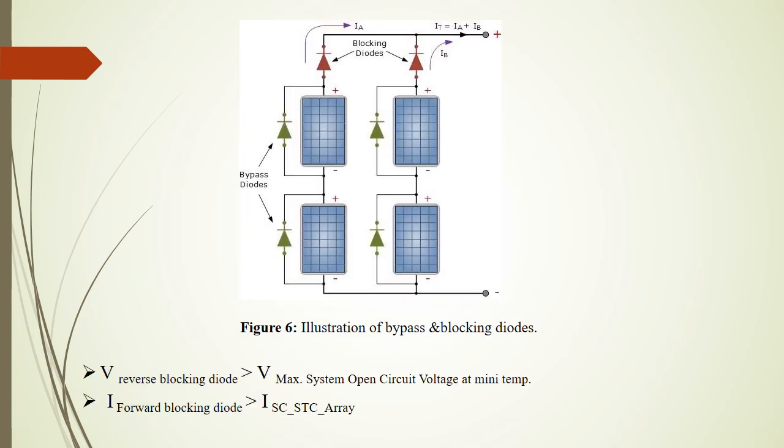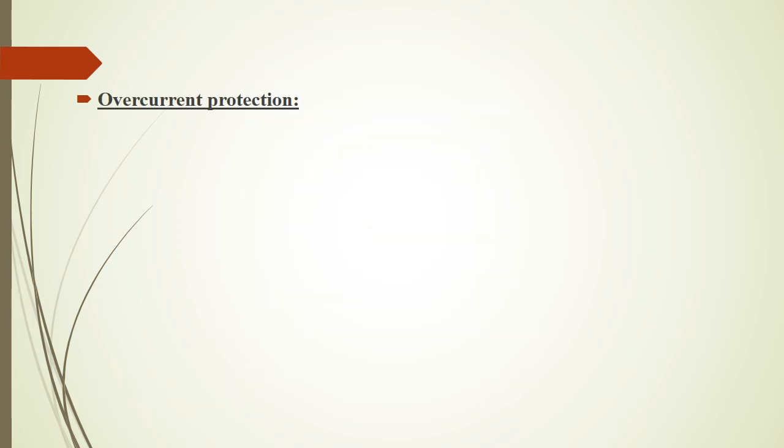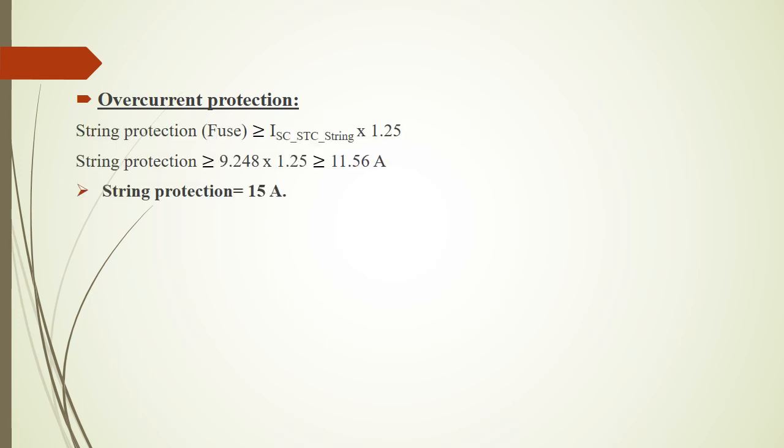Moreover, isolation diodes, or what are known as blocking diodes, are placed in series in each PV string wherever the array consists of two or more parallel branches, to prevent the current generated by other parallel connected PV panels in the same array from flowing back through the weaker or shaded string. Circuit breakers or fuses are commonly implemented to provide protection against the thermal effects of overcurrent.